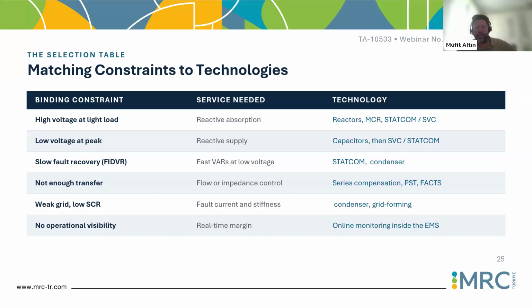So, of course, in power systems, we have voltage and frequency to control. And for the voltage, we have such binding constraints, as you can see in the table. You can say it's the source of the problem. The first one is high voltage at light load. We have this most of the time at night or when we have light load conditions. In this case, as a local phenomenon in that area where the light load is, there could be, depending on the planning or operational issues, some high voltage or excess reactive power. So we need to absorb this reactive power. We need to compensate it.